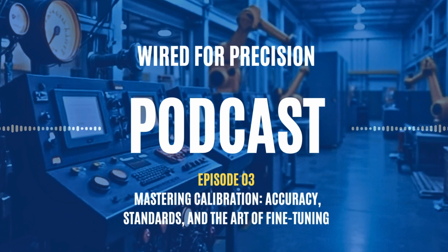2. Stability of the instrument. Some instruments, especially digital and newer models, have high stability and low drift over time. Others, like analog pressure gauges, can drift more quickly, requiring more frequent recalibration. 3. Manufacturer recommendations. Most equipment suppliers provide suggested calibration intervals. Always start with their guidelines and then adapt based on performance over time. Fourth, historical performance. If your instrument has a history of staying within tolerance, you may consider extending the interval. This is called interval optimization. On the other hand, frequent drift means you may need to shorten the schedule.